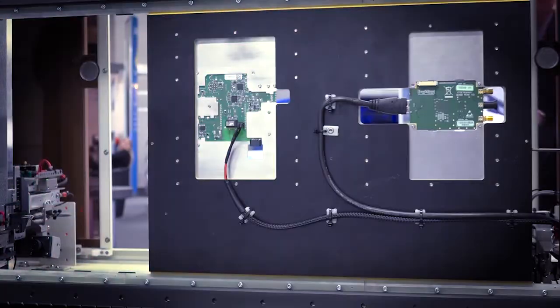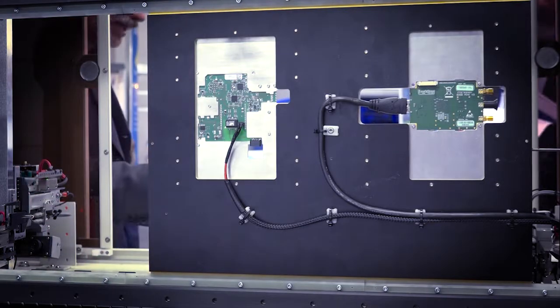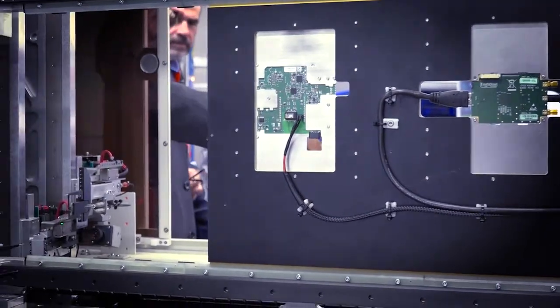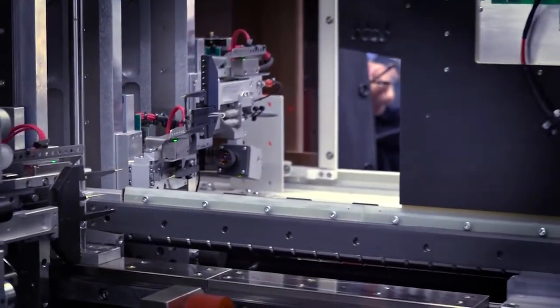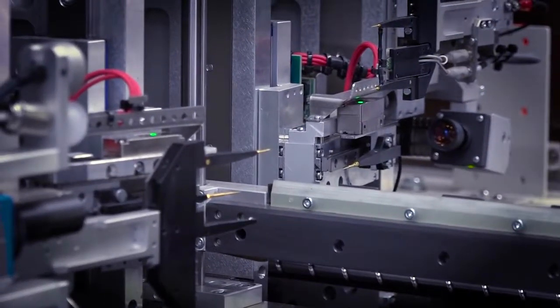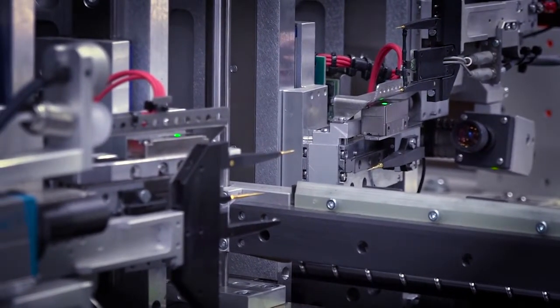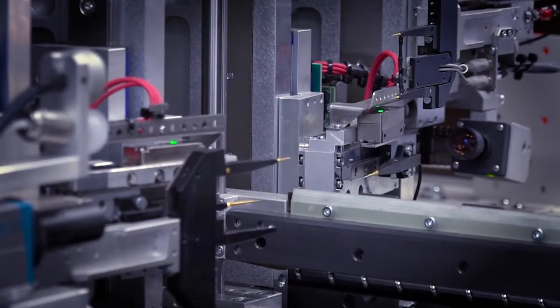Sure. So look, we're around at the other side of the machine now, where we can get a closer look at these probes. They're a very unique design. There's a dual probe. Can you explain to us a little bit about how they work? Yes. In fact, the ability of this machine to measure high frequency is because we have a specific path from the digital oscilloscope, which is on top of the machine doing the measurement, through the unit under test. We have special cables that are adapting the impedance of the measurement path, and we have an active probe where we have 2 needles, one taking the measurement and the other one grounding the signal.